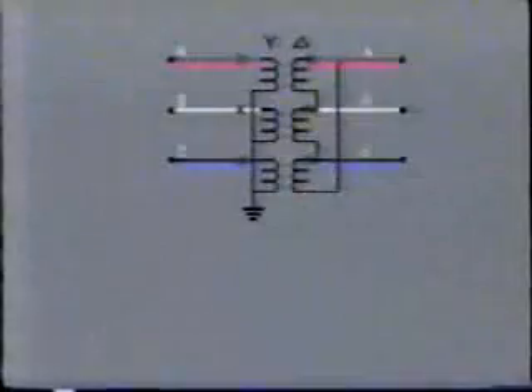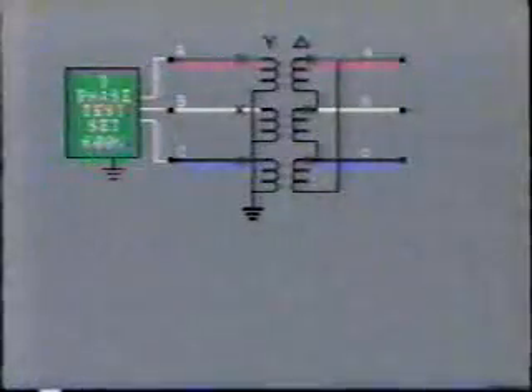However, this visual inspection is not always possible. For example, a three-phase transformer has internal connections. Also remember, there will be a phase shift between primary and secondary for a Y-delta connection. In most cases, phasing of the transformer would have been tested during installation by applying a low voltage, say 600 volts, to the high voltage side and measuring voltages on the secondary. Plotting the resultant phasor diagram will prove the voltage ratio, phasing, the phase shift, and phase rotation.